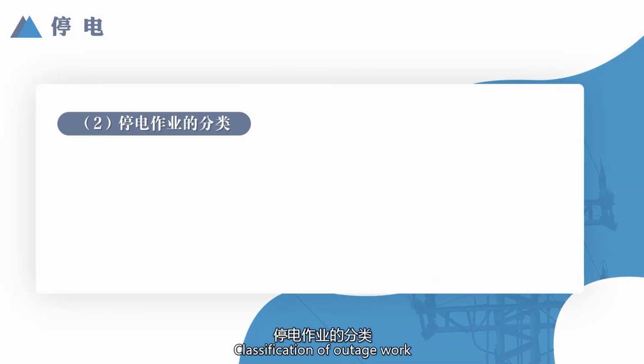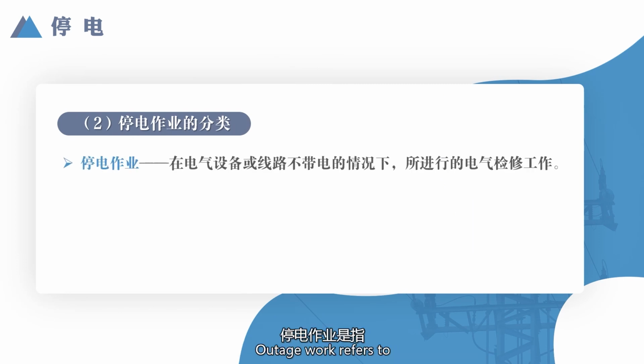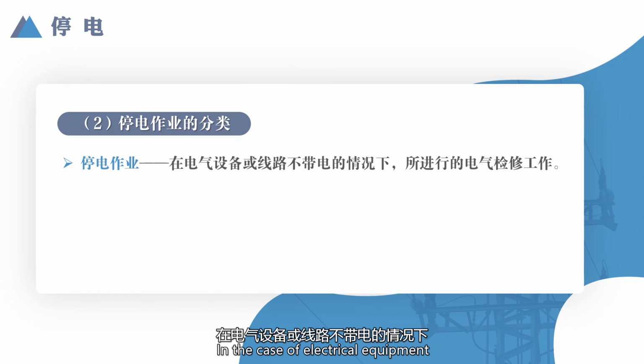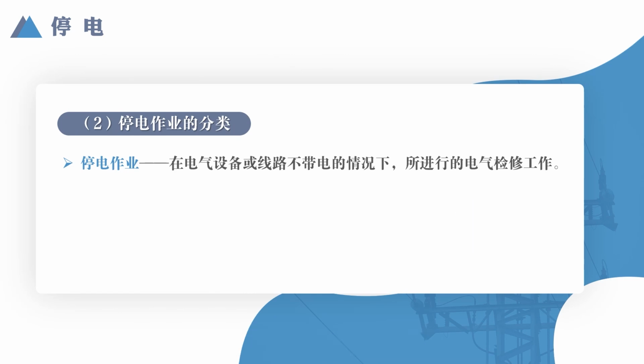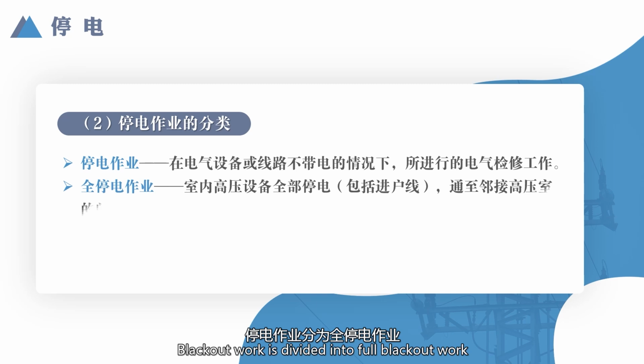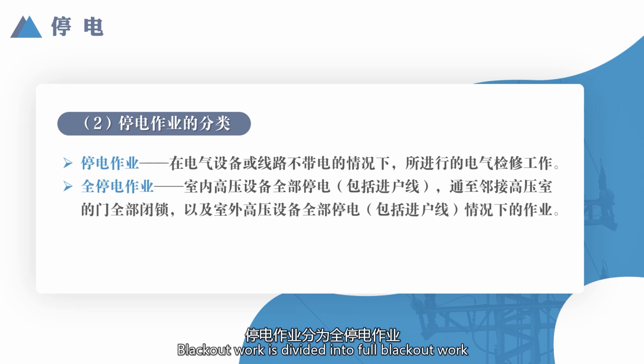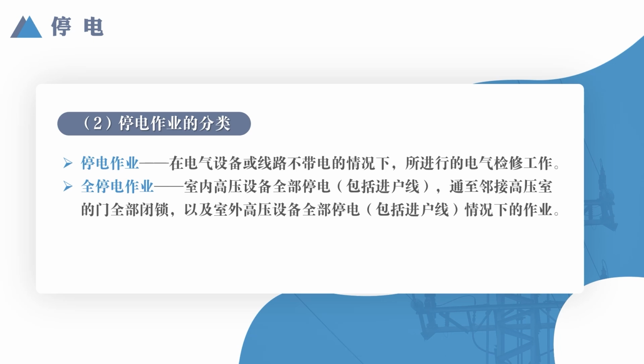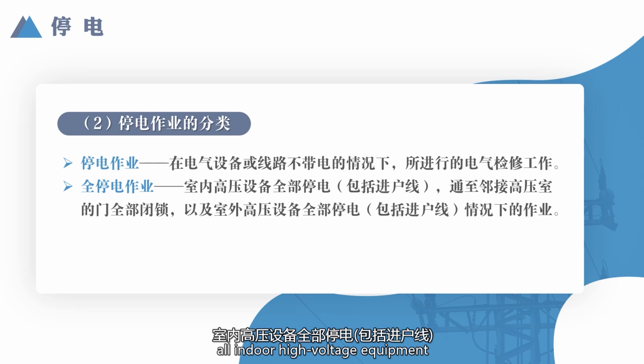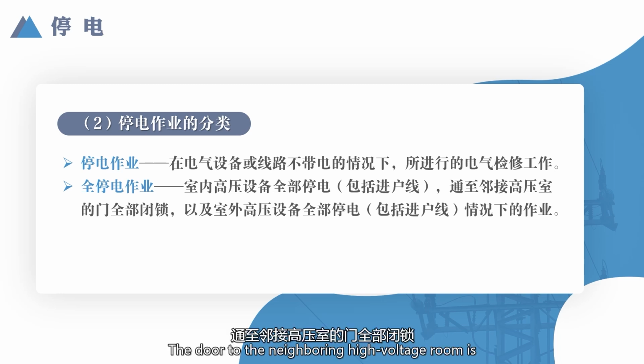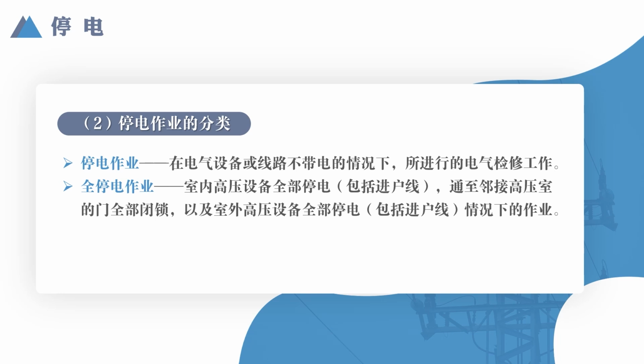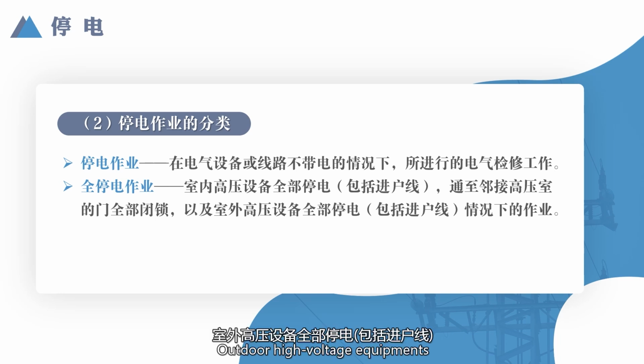Second, classification of outage work. Outage work refers to electrical maintenance work carried out in the case of electrical equipment or lines that are not energized. Blackout work is divided into full blackout work and partial blackout work. Full blackout refers to all indoor high voltage equipment being de-energized, including house wires.